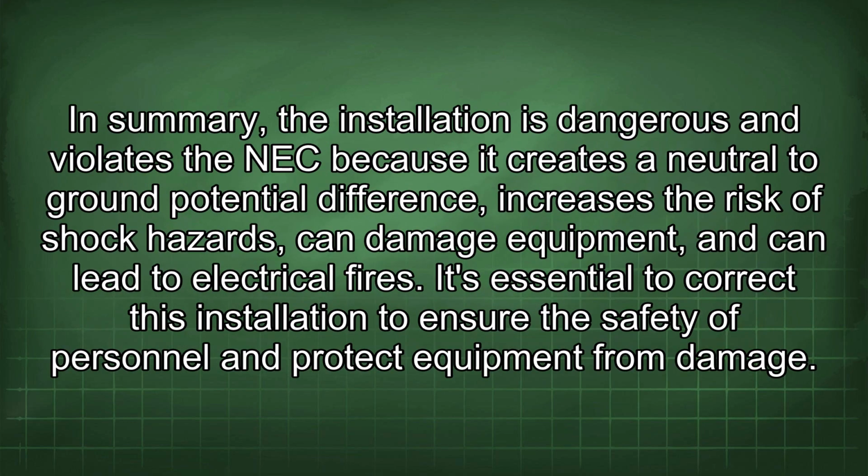In summary, the installation is dangerous and violates the NEC because it creates a neutral to ground potential difference, increases the risk of shock hazards, can damage equipment, and can lead to electrical fires. It's essential to correct this installation to ensure the safety of personnel and protect equipment from damage.